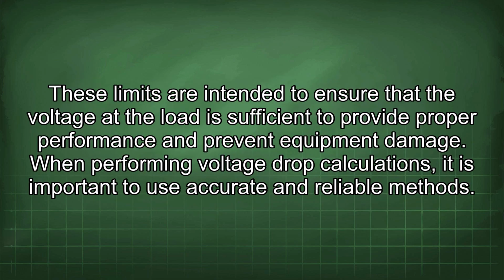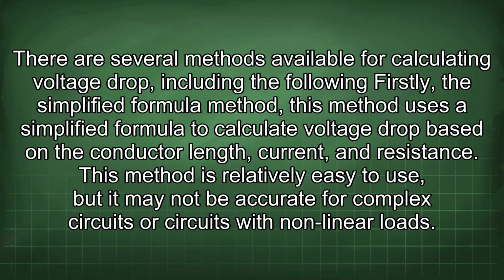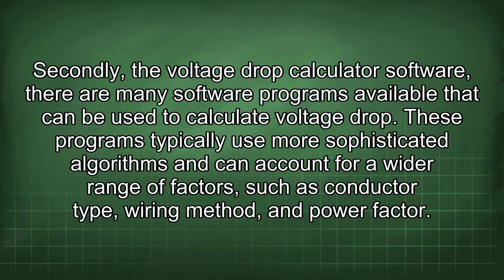These limits are intended to ensure that the voltage at the load is sufficient to provide proper performance and prevent equipment damage. When performing voltage drop calculations, it is important to use accurate and reliable methods. There are several methods available for calculating voltage drop, including the following. Firstly, the simplified formula method. This method uses a simplified formula to calculate voltage drop based on the conductor length, current, and resistance. This method is relatively easy to use, but it may not be accurate for complex circuits or circuits with nonlinear loads. Secondly, the voltage drop calculator software.